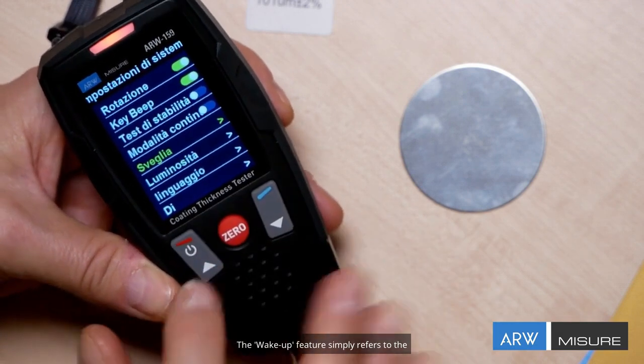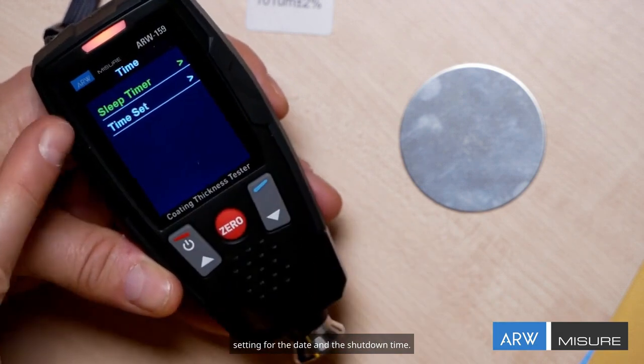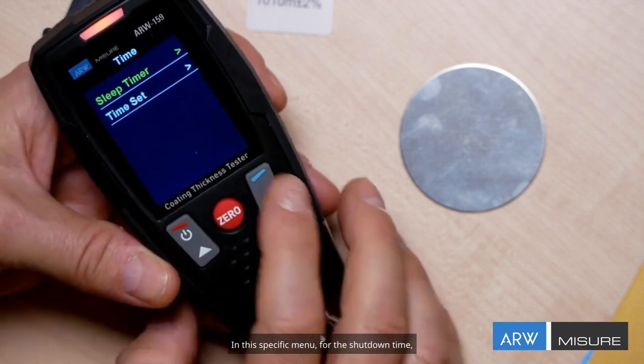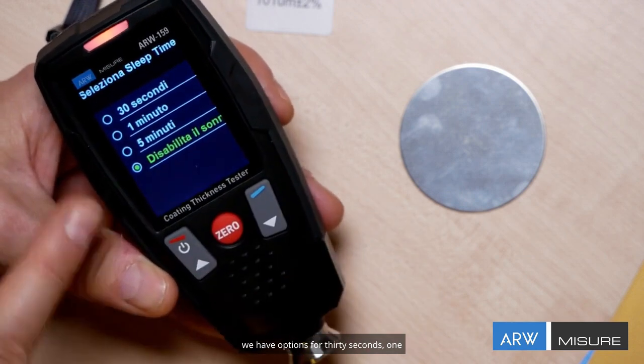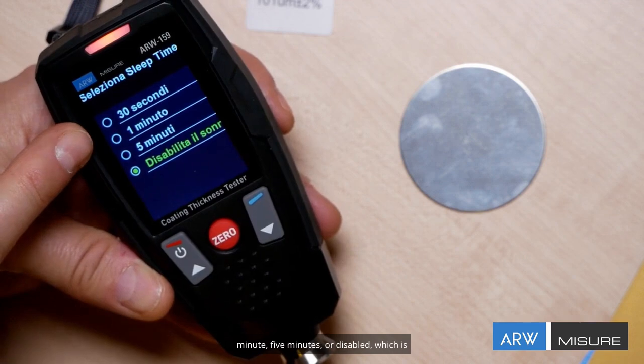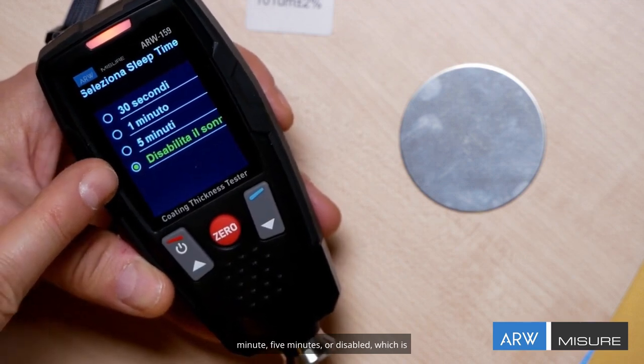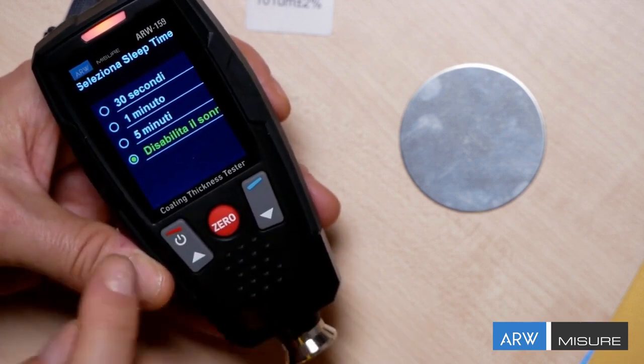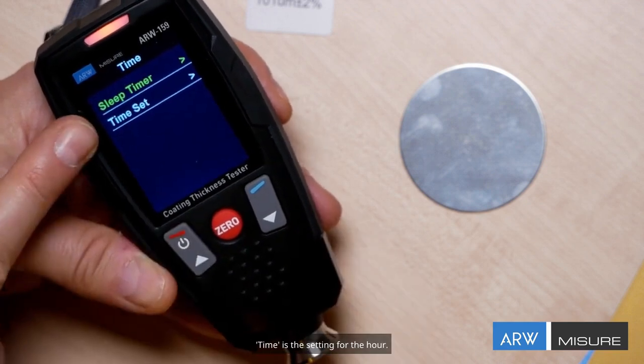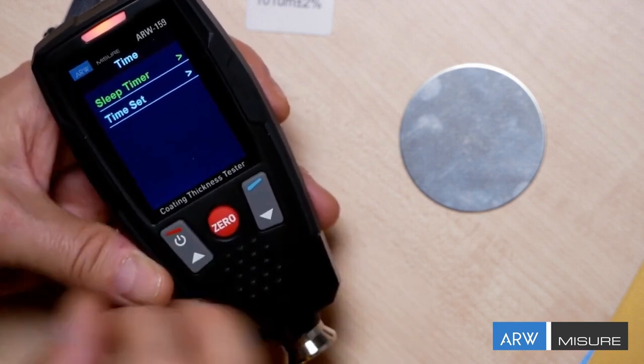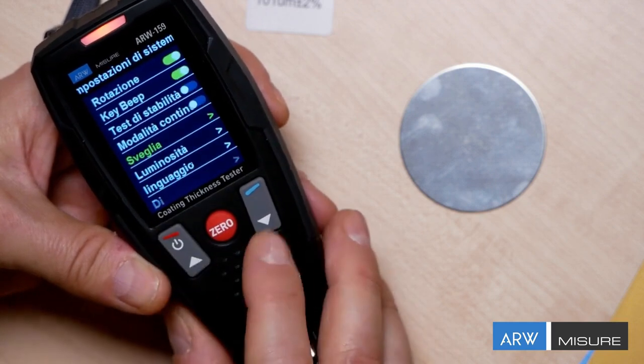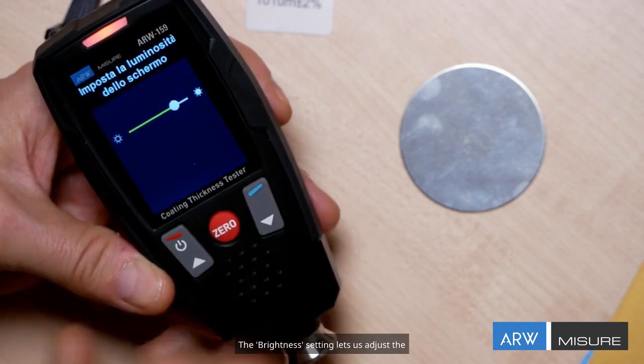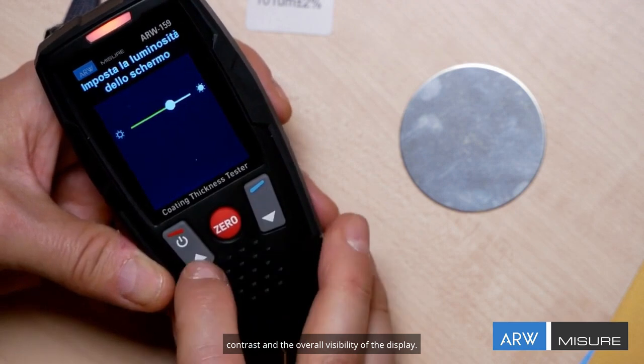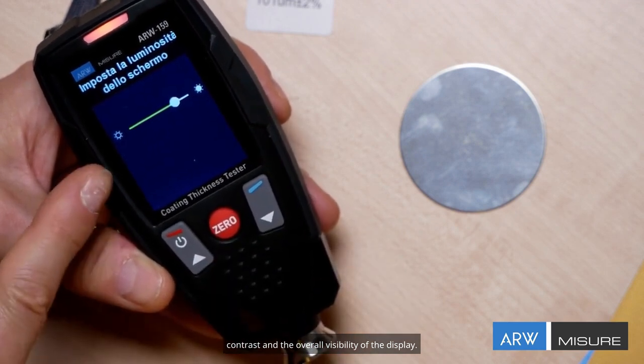The wake-up feature simply refers to the setting for the date and the shutdown time. In this specific menu, for the shutdown time, we have options for 30 seconds, 1 minute, 5 minutes, or disabled, which is how it is currently set right here. Time is the setting for the hour. The brightness setting lets us adjust the contrast and the overall visibility of the display.